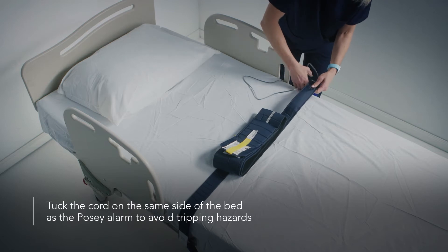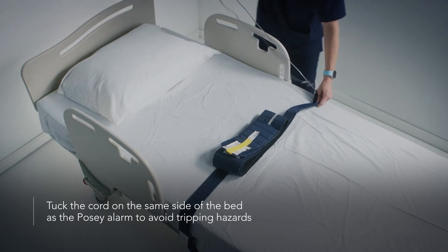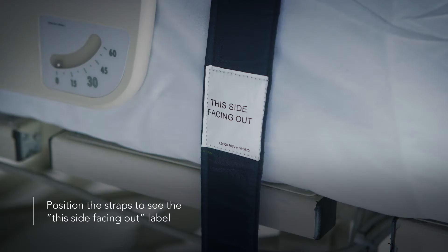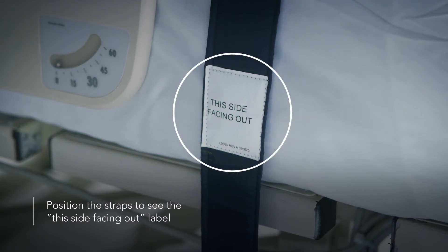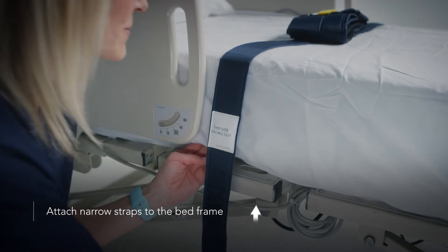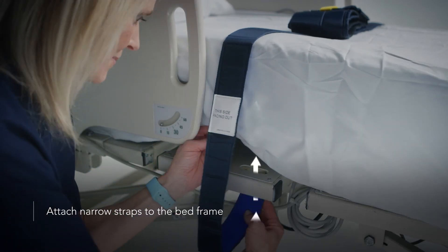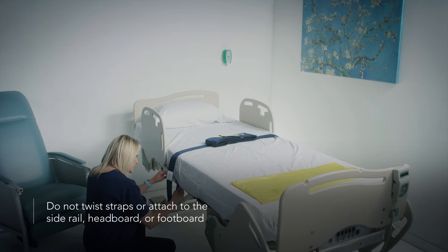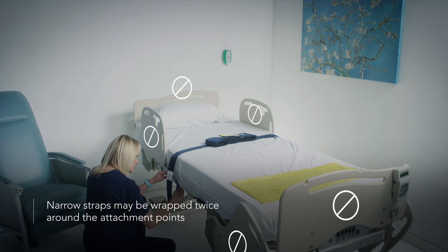Position the belt so the cord is on the same side of the bed as the Posey alarm. Position the straps so you can see the 'this side facing out' label. Attach the narrow straps to the part of the bed frame that moves with the patient. Do not twist the straps and do not attach them to the side rail, headboard, or footboard. The narrow straps may be wrapped twice around the attachment points to decrease the length of the strap.